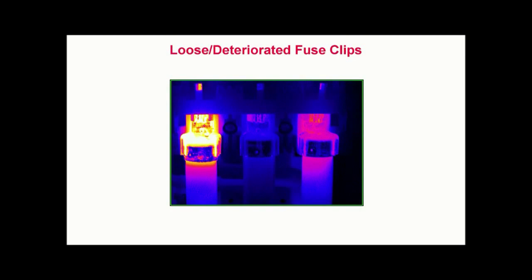Loose or Deteriorated Fuse Clips. In this thermogram of a low voltage disconnect switch, we see excess localized heating caused by loose or deteriorated fuse clips on the left and right fuses. This problem is common to low voltage devices and can lead to an unscheduled outage.